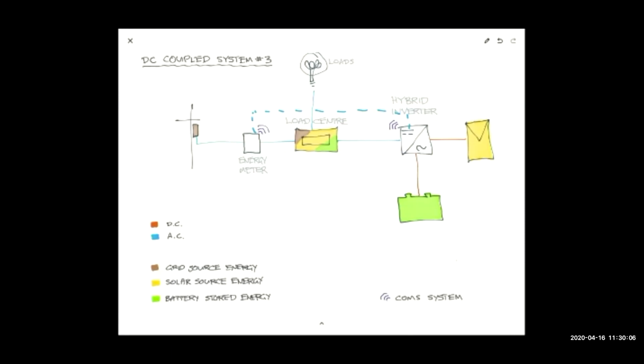So just to illustrate that scenario, here we go. The customer turns on their heater, so they've got a 2.4 kilowatt load that comes on. Initially, we will see that energy coming from the grid, 2.4 kilowatts. The communication with the hybrid inverter may take a few moments. It's not instantaneous, and that's for reasons of flicker. It will ramp up to try and displace that grid power. So it'll start to increase its output. The energy will be coming from the battery and the solar if the sun's shining at the same time, and they merge together internally, so we'll just draw it like that. It'll try to meet that load, produce the same amount of export, and therefore reduce the exchange from the grid to zero. That can take 10 to 30 seconds or so, but it will ramp up and match that exchange. So that meter is critical in that process.